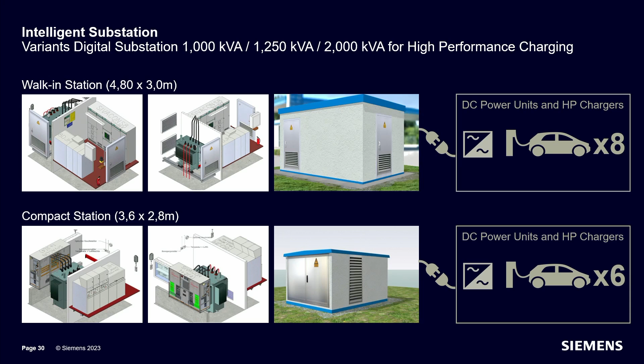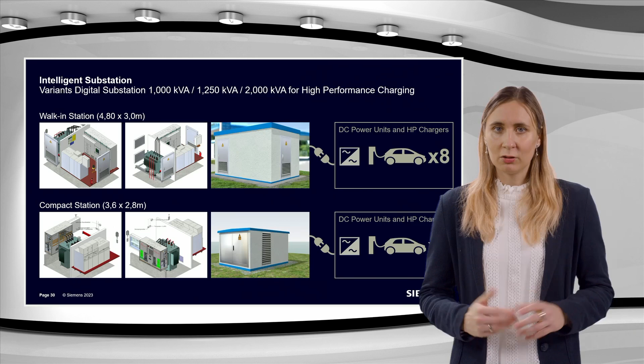We offer two types of stations: first, a walk-in station with concrete walls, or a compact substation with metal walls, depending on the transformer rating. The transformer rating is based on the charger requirement, for example if 8 or 6 high-speed chargers are required. Then the electrical infrastructure is designed as a complete solution containing medium voltage switchgear, low voltage switchgear, and a transformer inside, with the IoT application on the cloud on top.